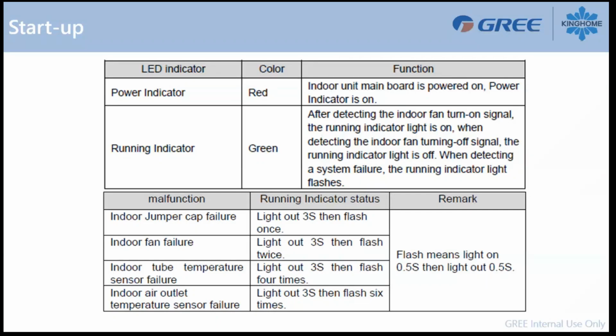For example, if you have changed a board and you forgot to change the blue jumper cap, right away you will have only one flash. So light out for 3 seconds, then flash once. Again, goes off, flash once. This means the jumper cap has failed, or you just forgot to replace it when you changed the board. If there's two flashes, this indicates an indoor fan failure. If the indoor tube sensor has failed, you will have 4 flashes. And if you forgot to attach the indoor air outlet temperature sensor, the one that comes with the duct heater, you will have 6 flashes. So that indicates the error code directly with the green LED.